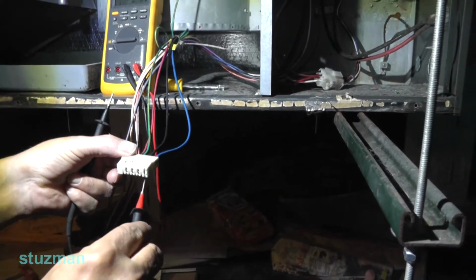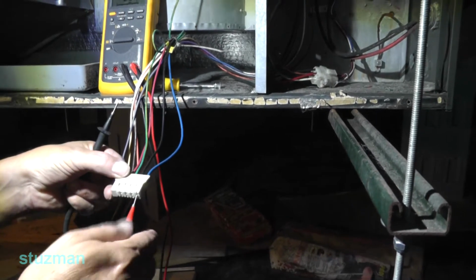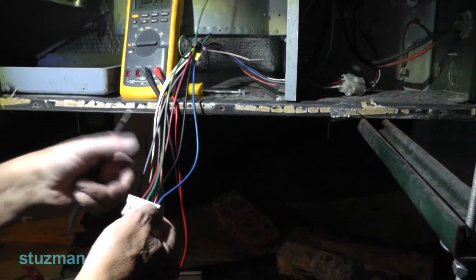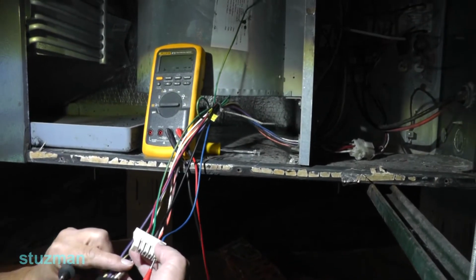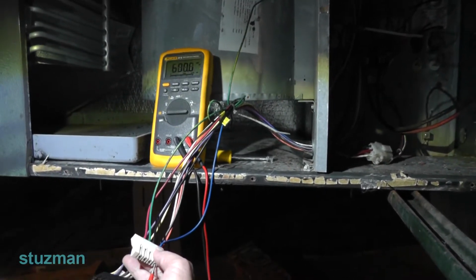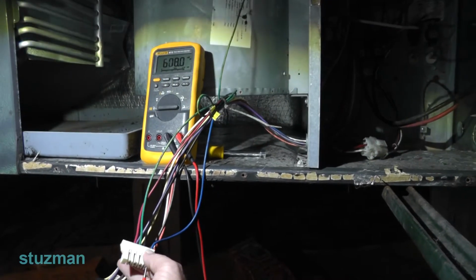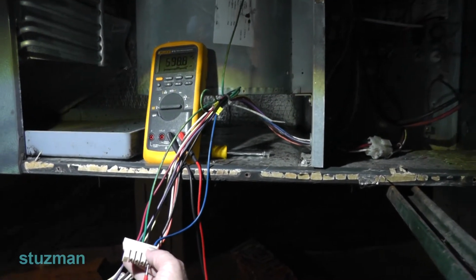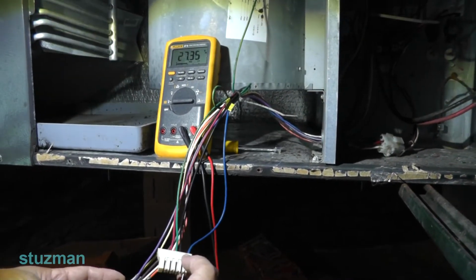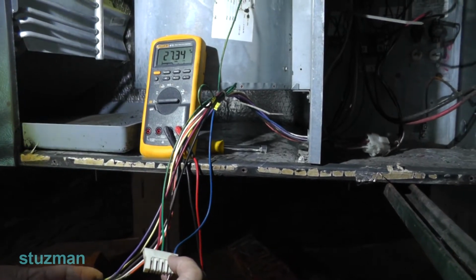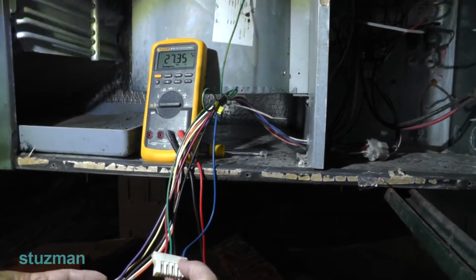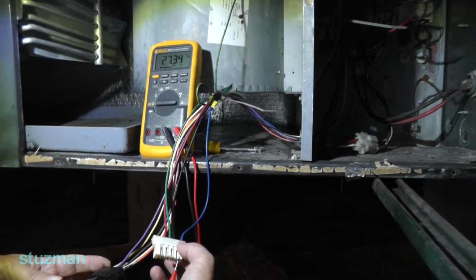So I'm going to check between the blue wire and the purple wire, and we should have 24 volts AC, if I can make a good connection. So you can see that I got 27 volts AC. So everything looks fine here.